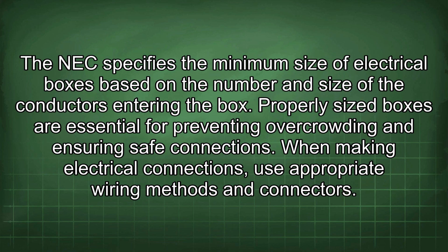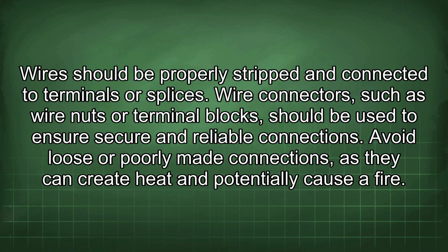When making electrical connections, use appropriate wiring methods and connectors. Wire should be properly stripped and connected to terminals or splices. Wire connectors, such as wire nuts or terminal blocks, should be used to ensure secure and reliable connections. Avoid loose or poorly made connections, as they can create heat and potentially cause a fire.